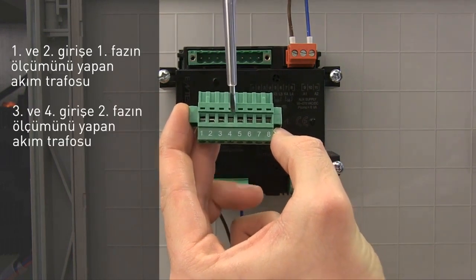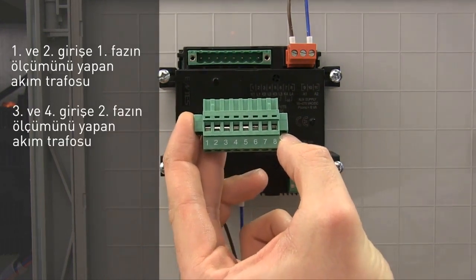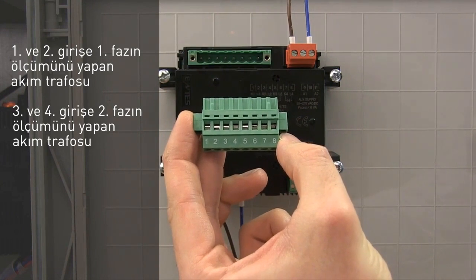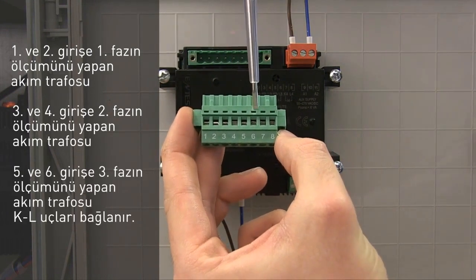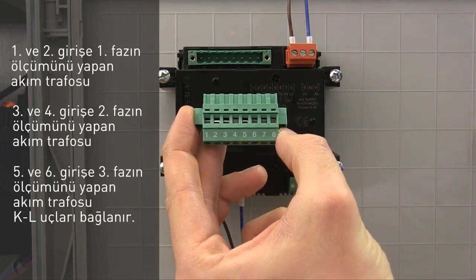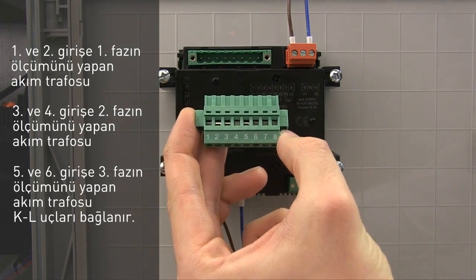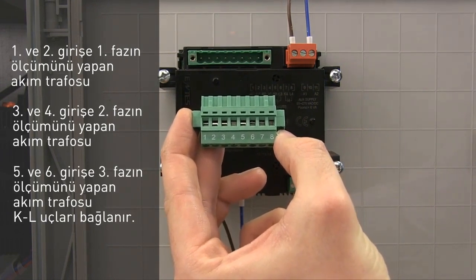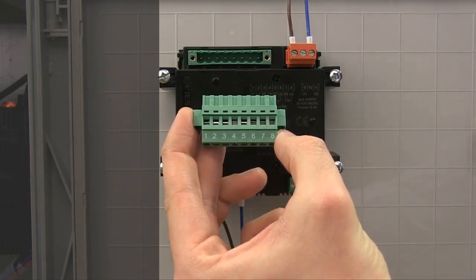The second phase transformer connects to inputs 3 and 4. The third phase transformer connects to inputs 5 and 6. We're placing the current transformer that measures the phase into the terminals.